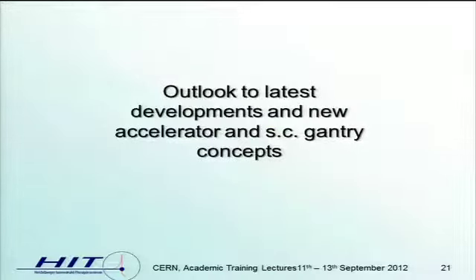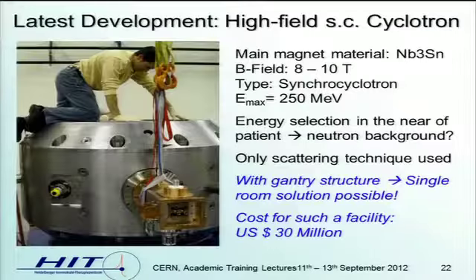So at last, an outlook to the latest developments, new accelerator concepts, and superconducting gantries. The latest development of this year coming up into operation are so-called high-field superconducting cyclotrons. What they have done, they used LHC cables to form a magnet for the main magnet of a cyclotron. And as you can see here, this 250 MeV synchrocyclotron, so it's a pulse machine, has only a diameter of 1.5. It's very compact. It's very lightweight for a synchrotron.